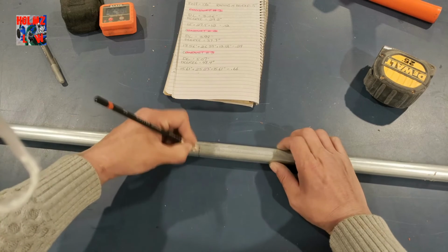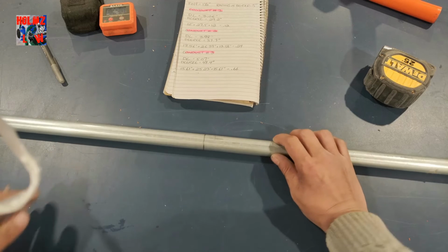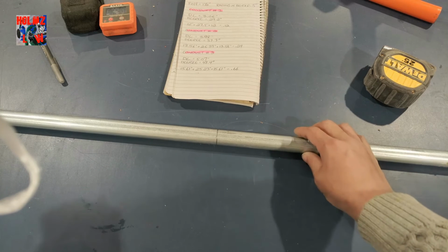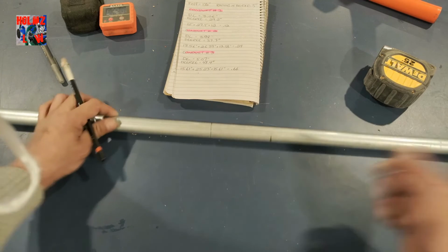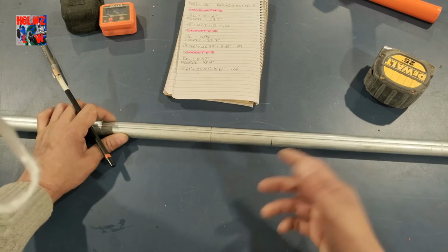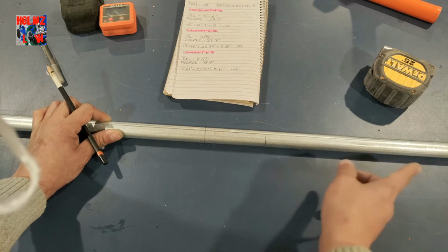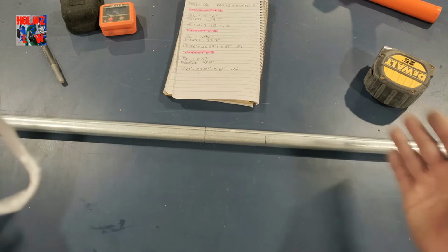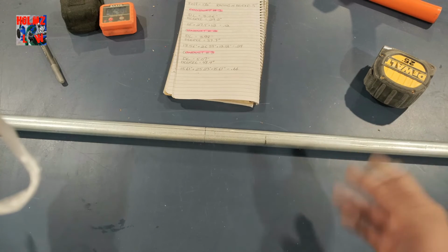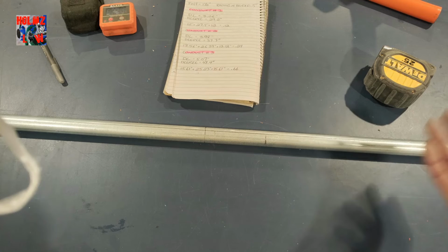mark. See, that's why this is such a good method, because if I wanted to, I could bend my first bend in one direction, and if it was too short of a pipe, I could flip this around and say, you know what, I want to bend it in that direction now and come up this way. Well, since we're bending on center, it doesn't matter. We can bend it in any way we want to because we know where the center is going to land, and we can just switch around our layout to suit us.